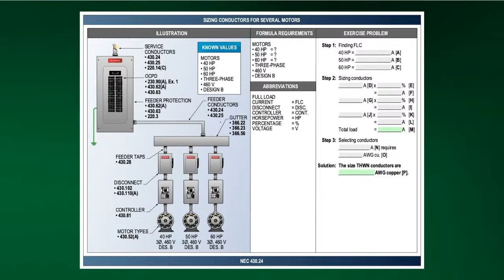As you look at this illustration, you're going to see we're showing a feeder where it's going over and supplying two or more motors. We tell you in order to size that overcurrent device, you look at 430.62A. But if I'm sizing the feeder conductors, I'll look at 430.24.